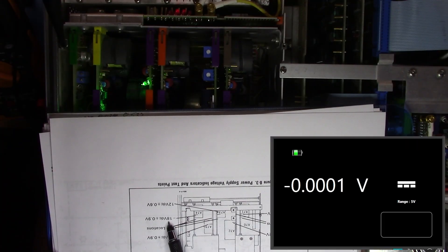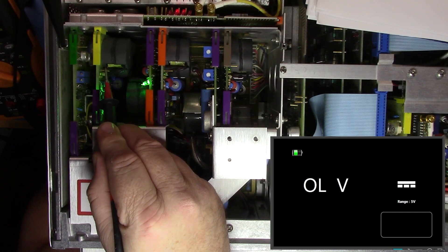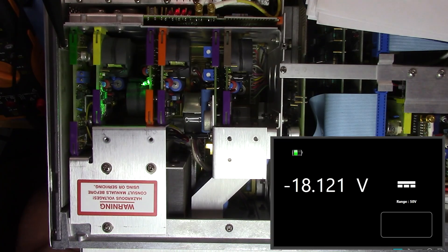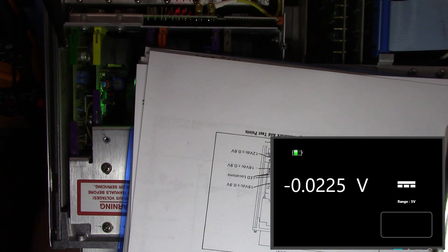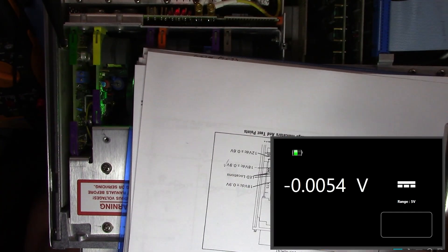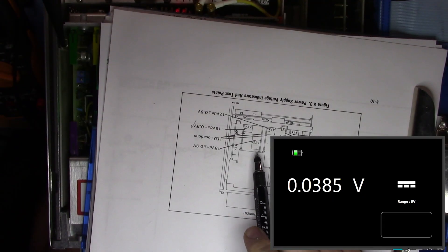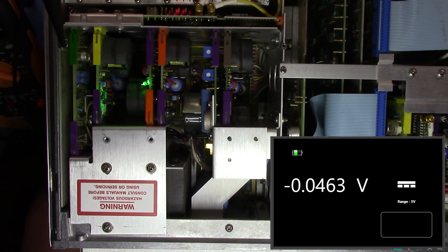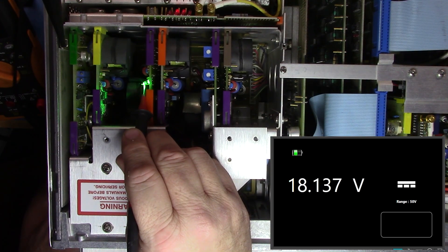Alright so the first one let me get my pen. So the first one we're going to look at is A74 here and it is 18 volts DC plus or minus 0.9 of a volt. So let's go take a look and that is minus 18.121. So that one is good so we'll tick that. Now the next one across A37 A73B and it should be 18 volts positive plus or minus 0.9 of a volt. So let's take a look at that. And it is also 18.138 so 18.14. So we're good there.